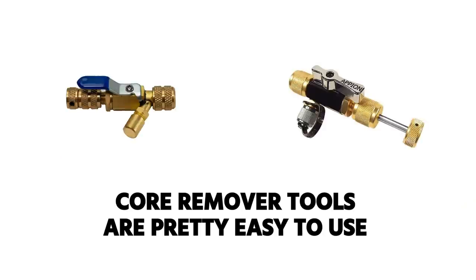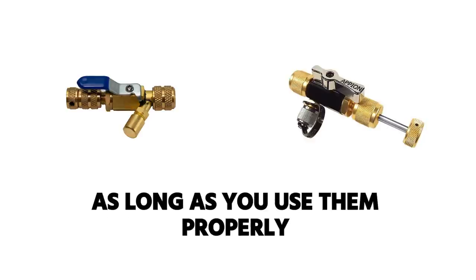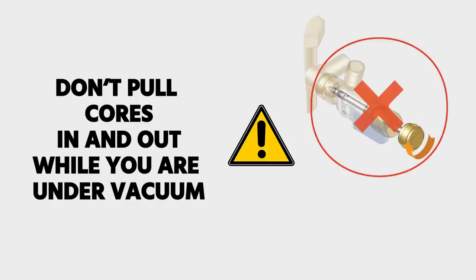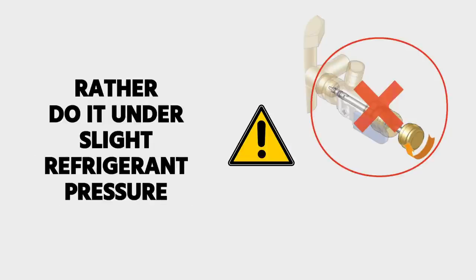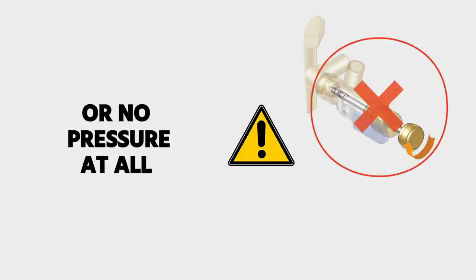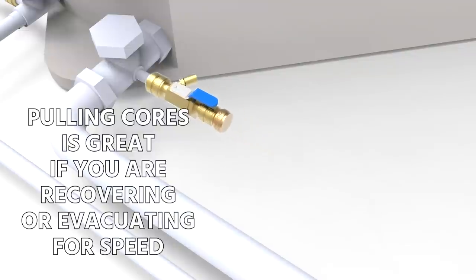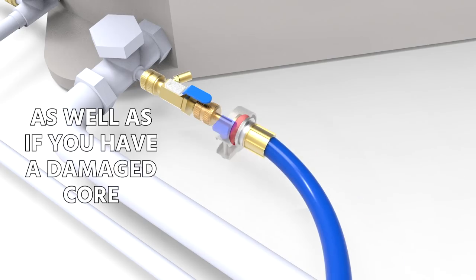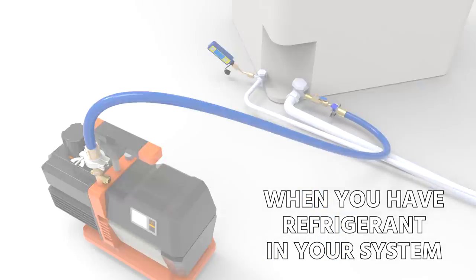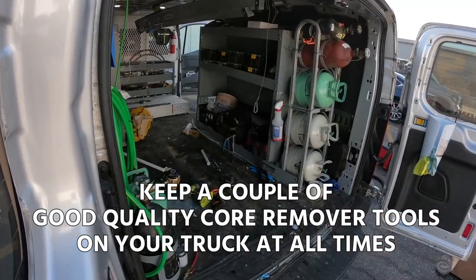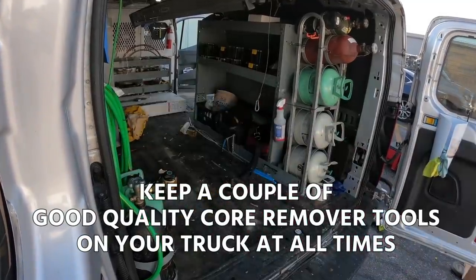So that's it. Core remover tools are pretty easy to use, so long as you use them properly and make sure not to try to pull cores in and out when you are under vacuum, but rather do it under slight refrigerant pressure or no pressure at all if the system has completely been recovered. Pulling cores is great if you are recovering or evacuating the system for speed, as well as if you have a damaged core when you have refrigerant in the system. So definitely keep a couple good quality core remover tools on your truck at all times.